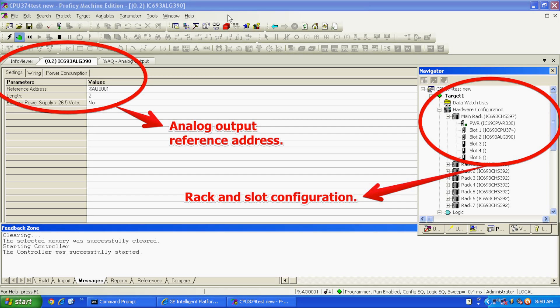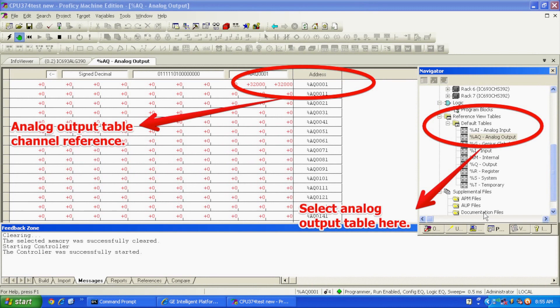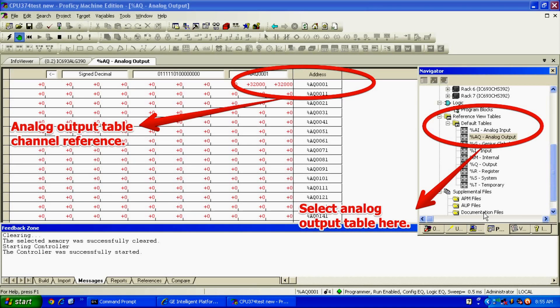Once that's configured, I'm going to go down to my reference view tables and expand that. Below that is default tables — you can expand that. The second selection down is %AQ, or analog output. You can either double click on that or right click and open, and then you're looking at your output table. The top right-hand corner is where the addresses start at analog output 0001. I've already placed a value of 32K, or 32,000, in both addresses 001 and 2.